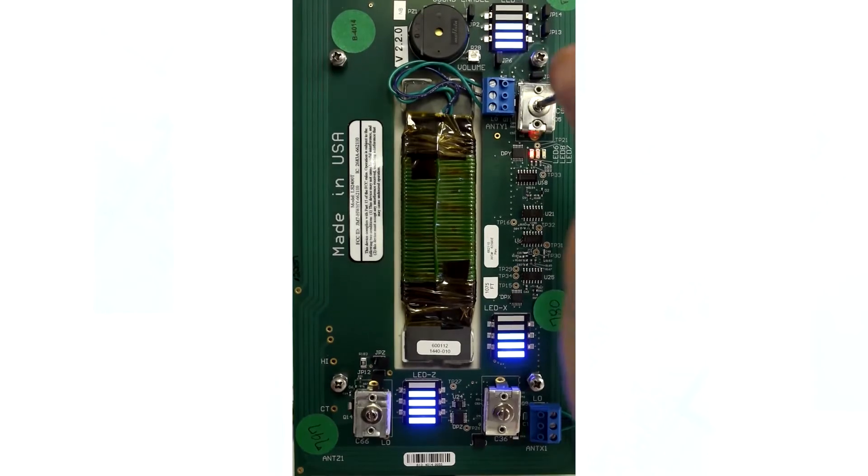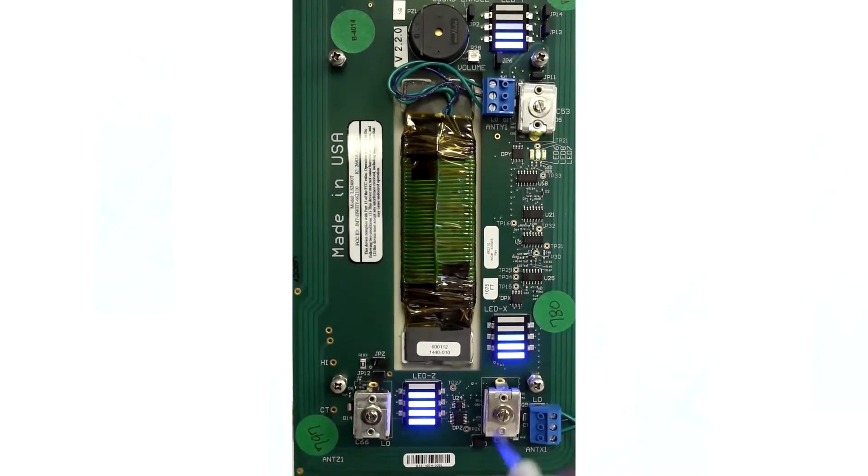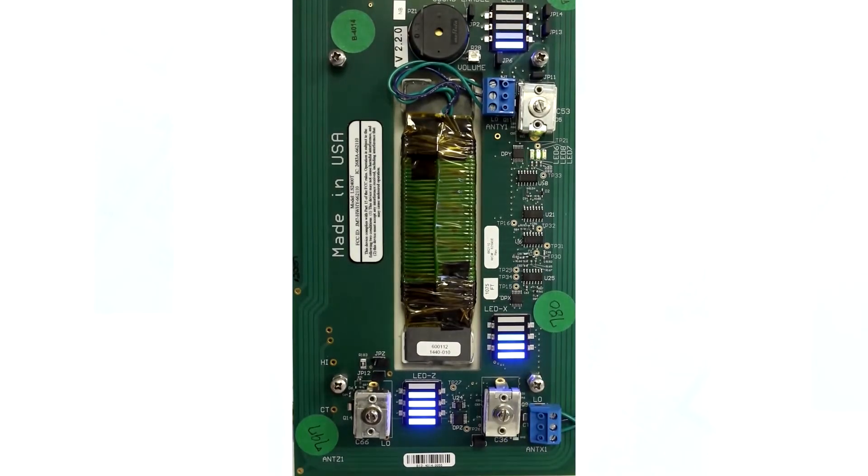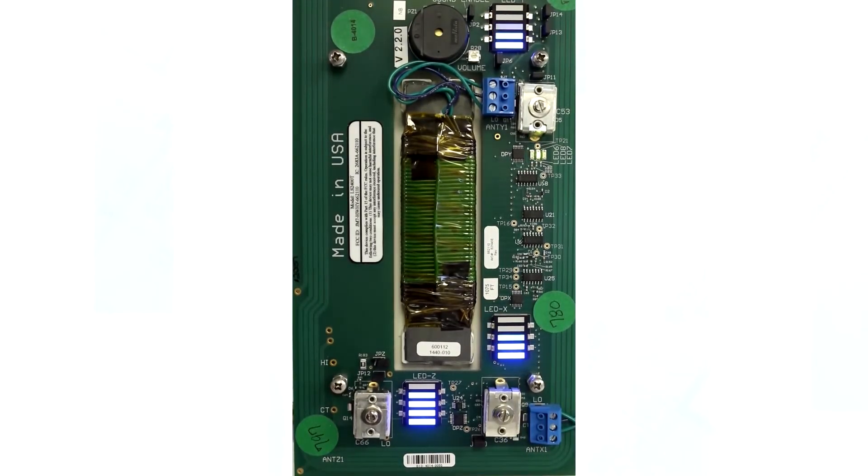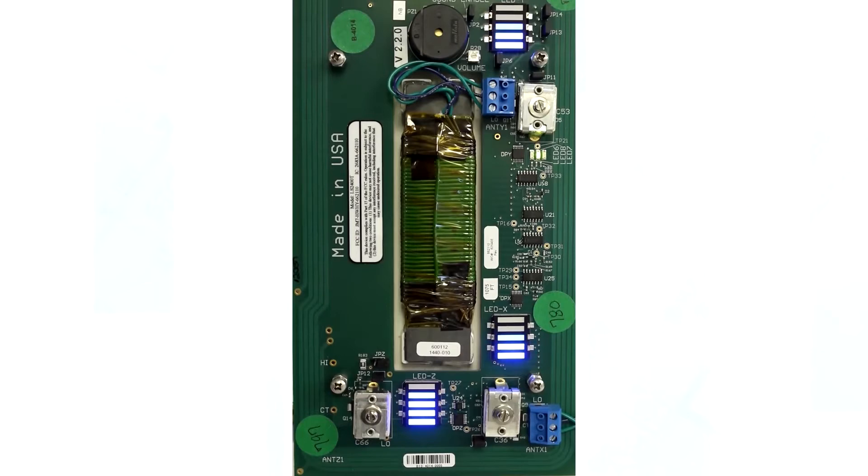The goal of tuning the door controller is to achieve phase lock. This is accomplished by fine tuning each of the tuning capacitors clockwise or counterclockwise until only a solid green LED is illuminated. Phase lock is indicated by only a solid green LED. If you are seeing red LEDs on either side, continue tuning.